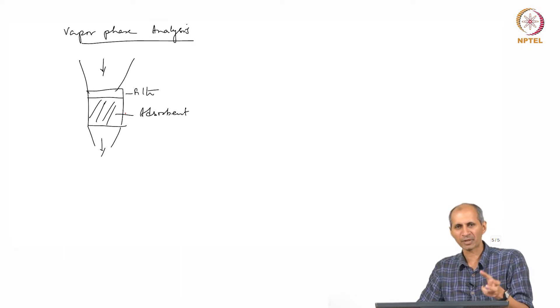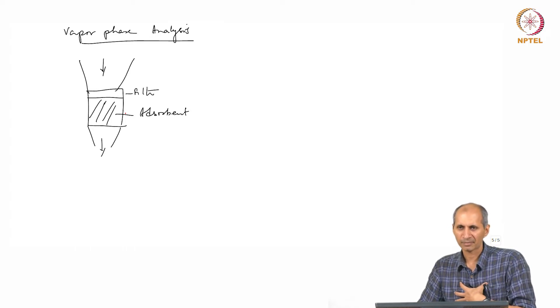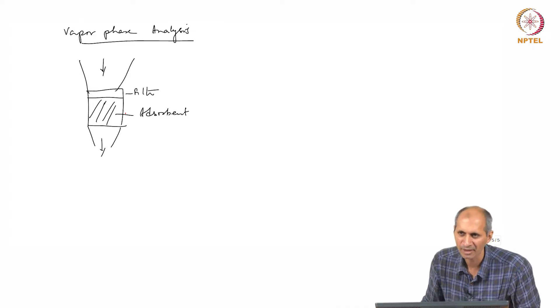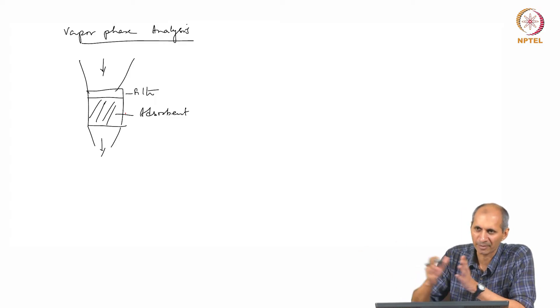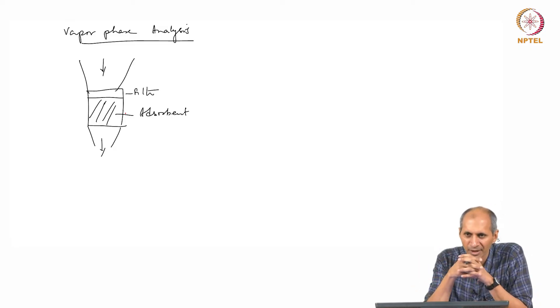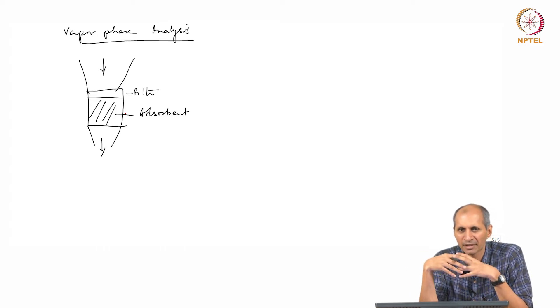The sampling material in a filter paper over a period of time, and the reason we're doing that is - we have instruments like real-time instruments. But if you're doing the PM method with the filter, why are we doing it over a period of time? Why do we need to accumulate sample? Because quantifiable mass, we need to measure it, the mass is measurable. Below detection limit, it's not easy to measure. Preferably I would like to just take this vapor sample as it is and measure it.